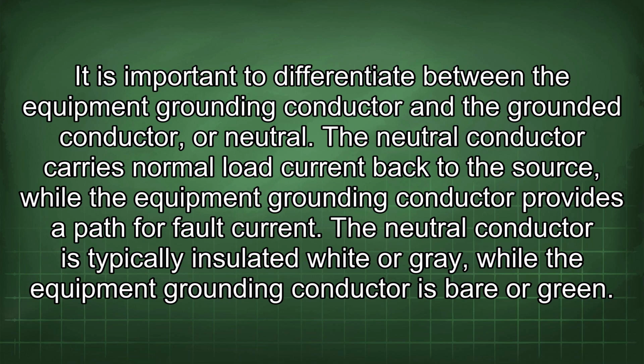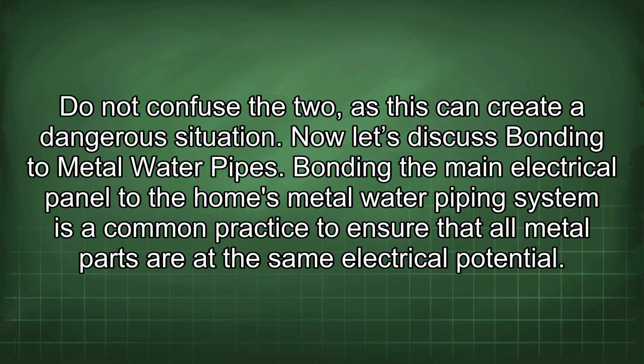The neutral conductor carries normal load current back to the source, while the equipment grounding conductor provides a path for fault current. The neutral conductor is typically insulated white or grey, while the equipment grounding conductor is bare or green. Do not confuse the two, as this can create a dangerous situation.